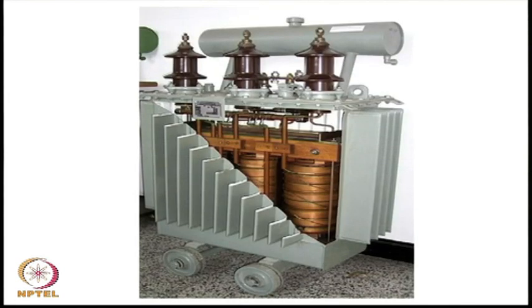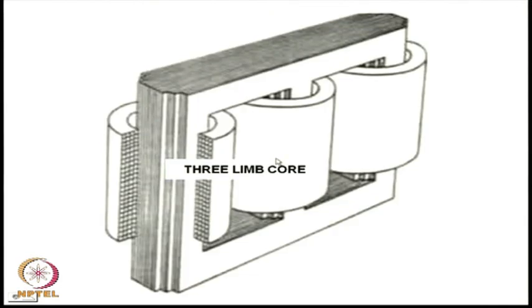So, if we look at a cutout view of a transformer, we find that inside the tank we find the core of the transformer, the windings, the terminals, and there is an overhead conservator like this. The essential part of the transformer consists of a core with windings on the limbs.